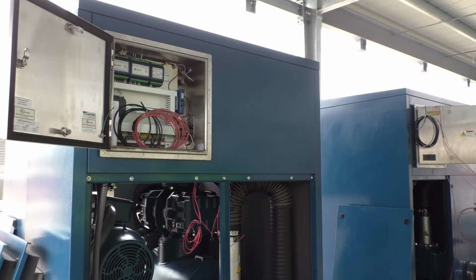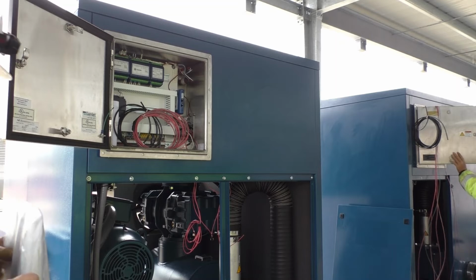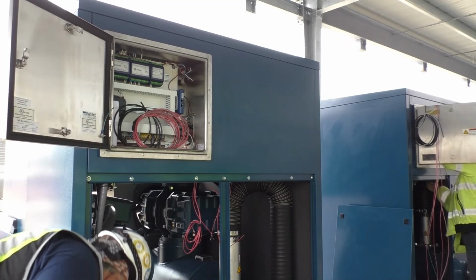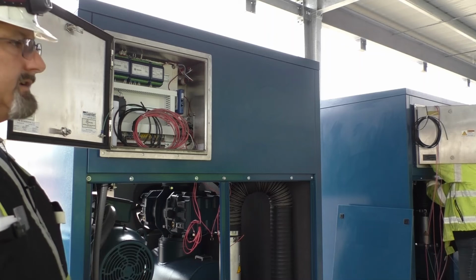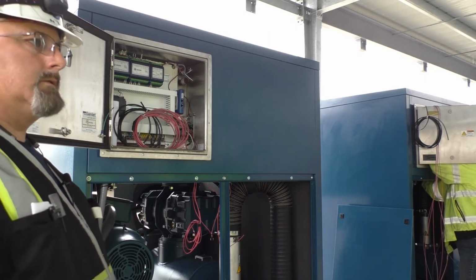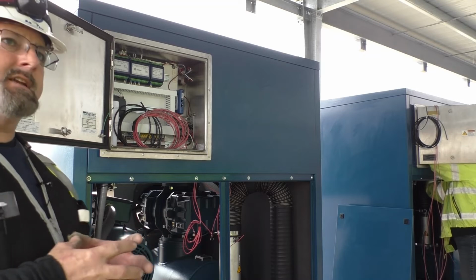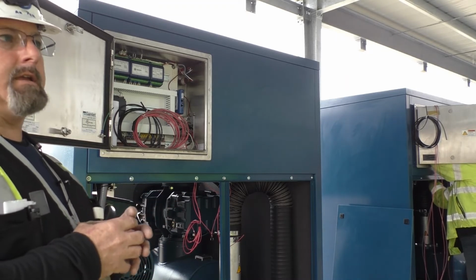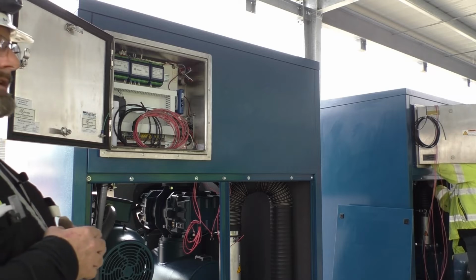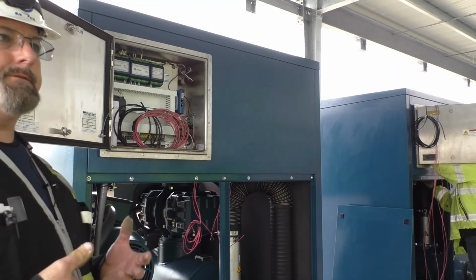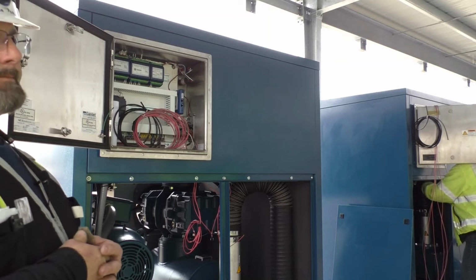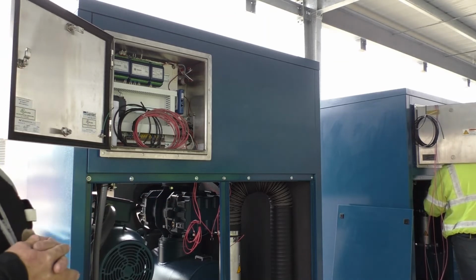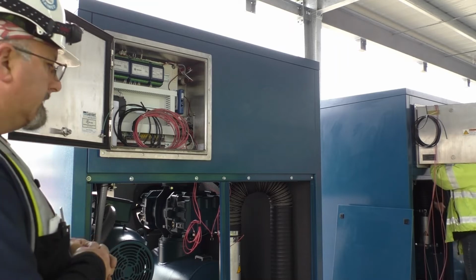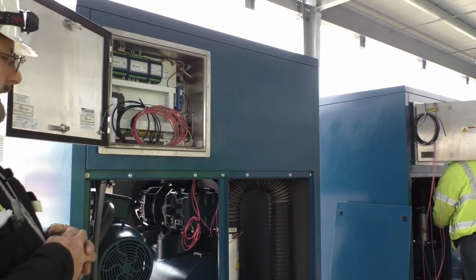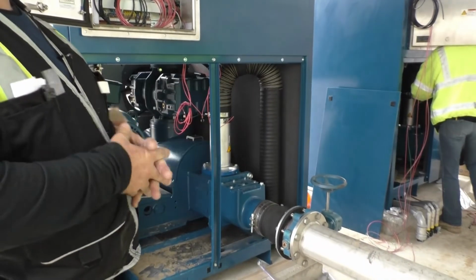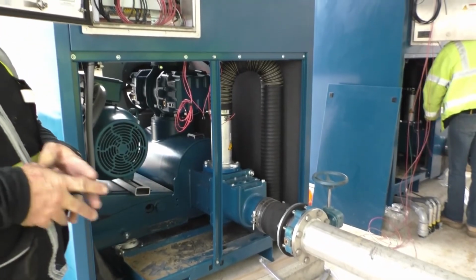It doesn't go in depth on repair because as far as disassembly of the stage itself, it needs to go back to our shop, because those gears that you've seen in that picture are hydraulically installed and hydraulically removed. If you were to just try to take a puller and pull those off, you would destroy those shafts. Trust me, people have tried, and they ended up having to buy new blowers because of it. So now we do have other authorized repair shops, but if you contact us, then we can relay that information to you if it doesn't come directly back to us.